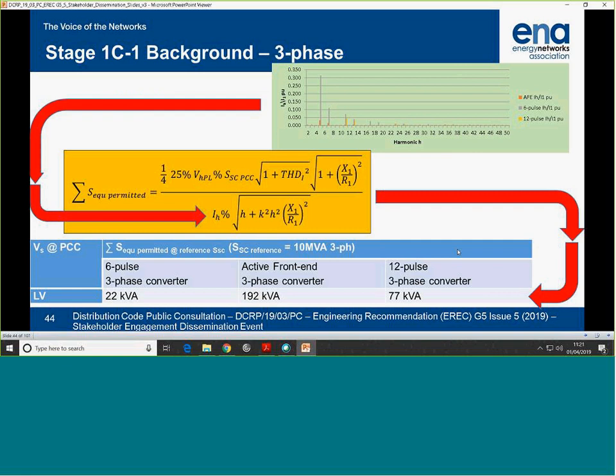The way it's been derived, you might say, well, where does that come from? The assumed emission profile is on the top left. You've got emission, which is used, and the key thing here is THD now in there. It wasn't in old calculations. A factor is taken account of as well, the ratio is in there. The key thing is that quarter factor. What we're saying here is we've got 25% of the planning level left to use up. That's the first point. And we're now saying we're going to divide that by 4. So this item is going to get 1/4 of that.